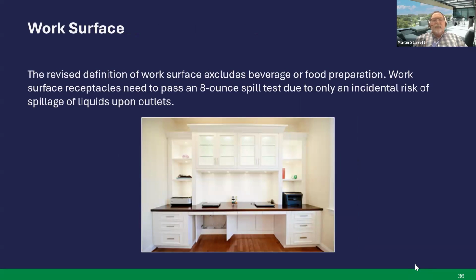Work surface. The revised definition of work surface excludes beverage or food preparation, unlike the countertop, which includes those. And there again, there's an informational note that leads you to a UL listing. These work surface receptacles need to pass an 8-ounce spill test due to only incidental risk of spillage of liquids upon outlets. A good example: if I installed a pop-up in a work surface, it wouldn't have to meet the listing requirements of a counter because of the spill. But if I put a work surface listed receptacle in a countertop, then I would have a code violation.